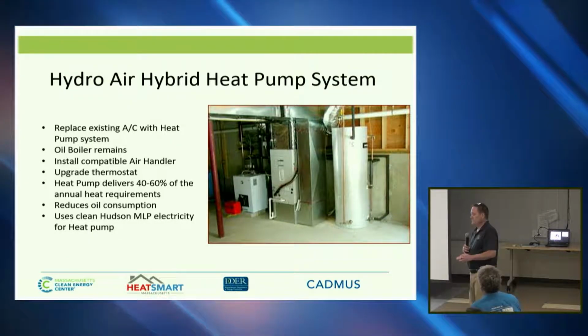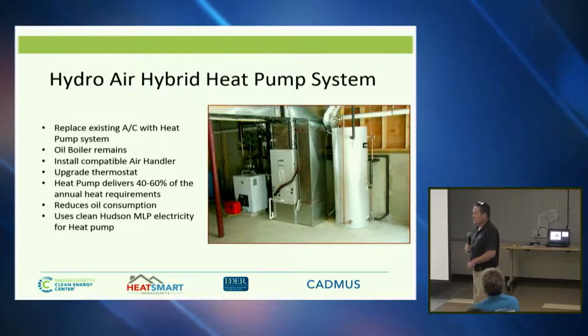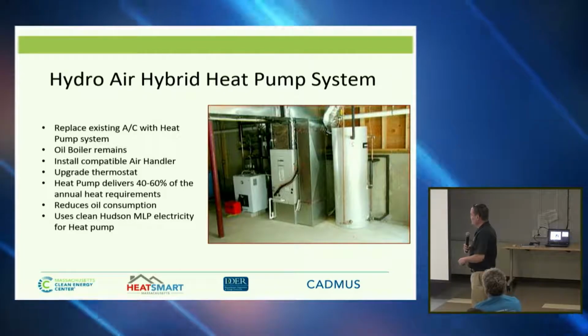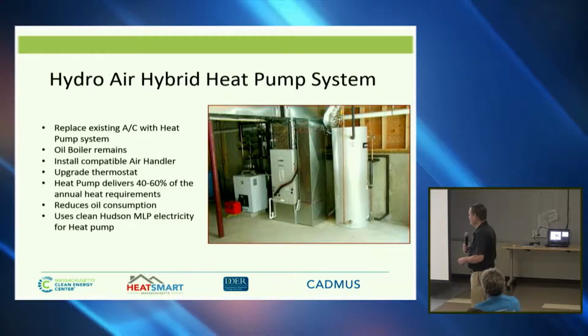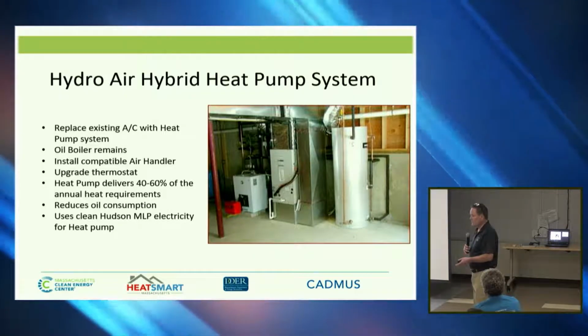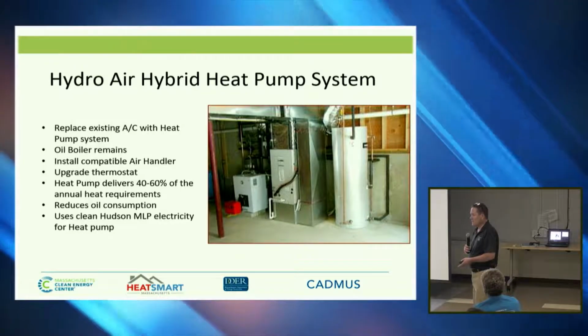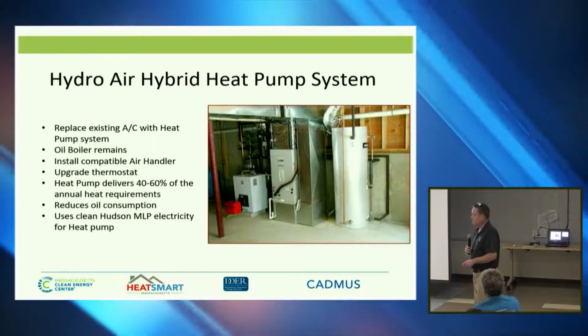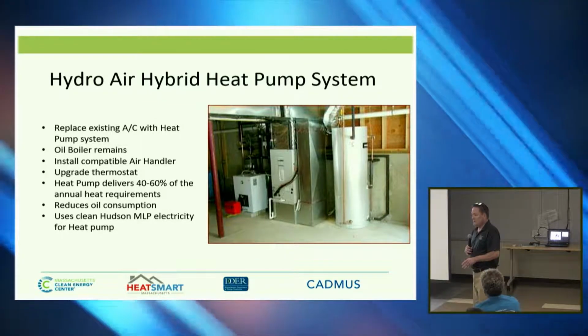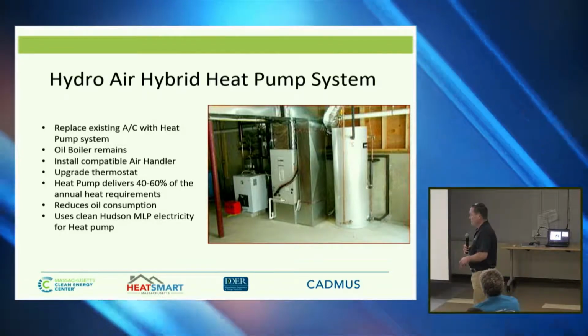This is another style of system that's very popular in the area, in houses built in the 1990s through the 2000s: a hydro air heating system. I've been up to see some of these here already. On the left you have an oil-fired boiler with the orange burner box on the front. The middle piece is an air handler, which blows heated and cooled air through your home, and on the right is an indirect-fired water heater. There's a lot of homes in the local area built in the last 25 years with this system, and they're all getting old enough now that they have to be replaced.